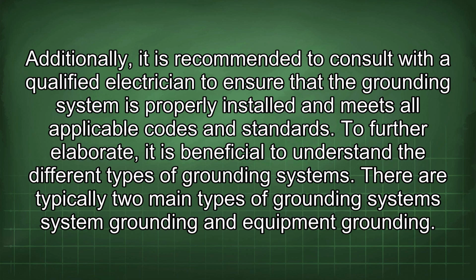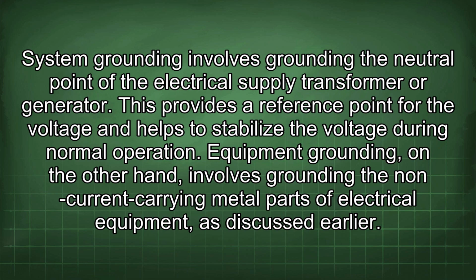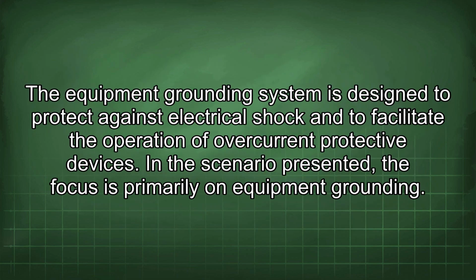To further elaborate, it is beneficial to understand the different types of grounding systems. There are typically two main types of grounding systems: system grounding and equipment grounding. System grounding involves grounding the neutral point of the electrical supply transformer or generator. This provides a reference point for the voltage and helps to stabilize the voltage during normal operation. Equipment grounding, on the other hand, involves grounding the non-current carrying metal parts of electrical equipment, as discussed earlier. The equipment grounding system is designed to protect against electrical shock and to facilitate the operation of overcurrent protective devices.